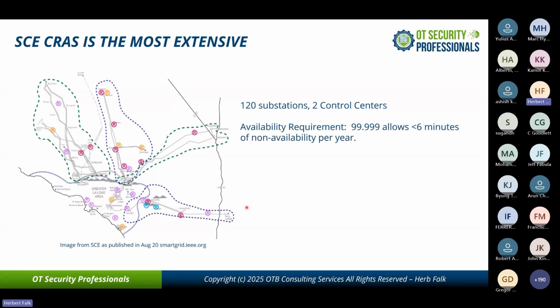So let's talk about SCE. It's the most extensive R-GOOSE system that I know of, and I was the original architect of this when I was at Cisco. Its availability requirement is 5 nines, meaning it can only have about 6 minutes of non-availability per year. Now think about designing a system for that. Some of the substations are 1,000 miles away, communication distance, from the control centers that are centralizing this protection.